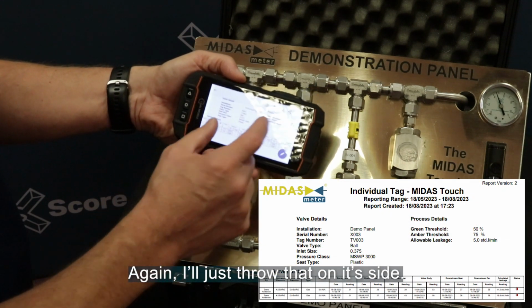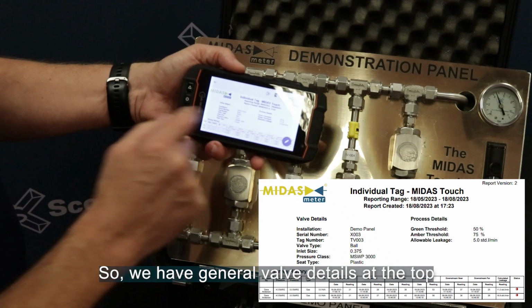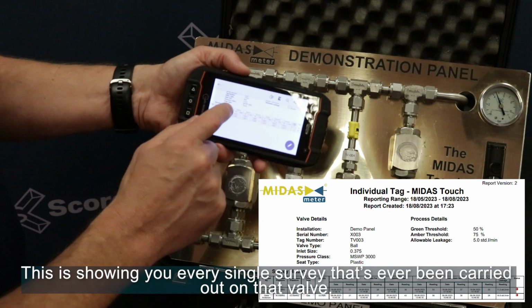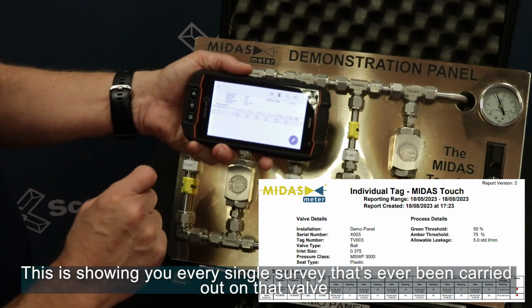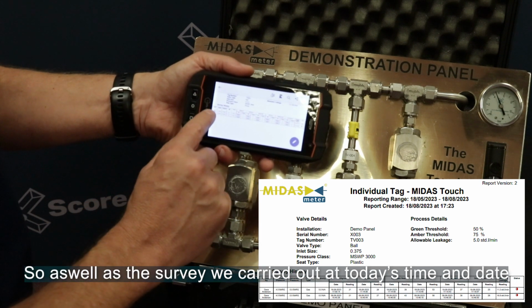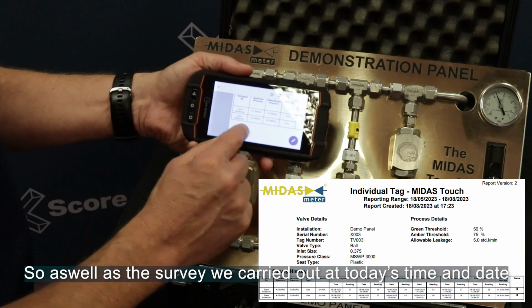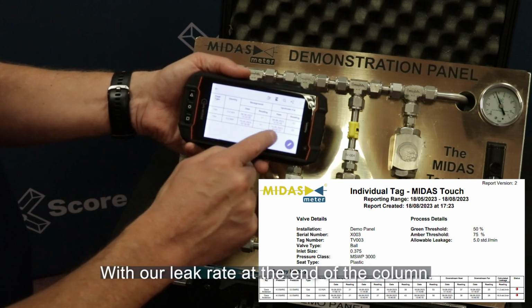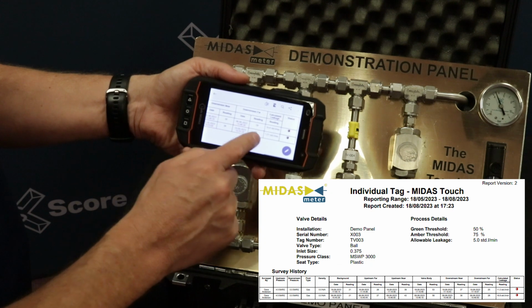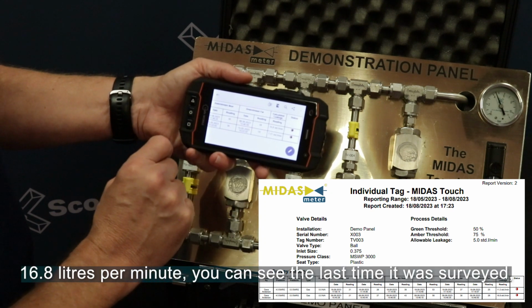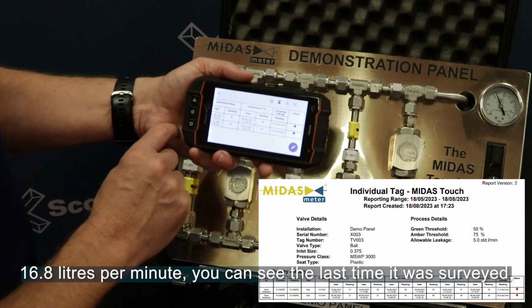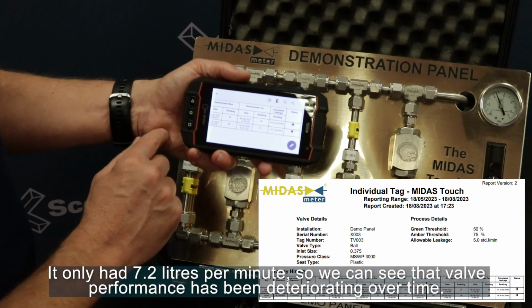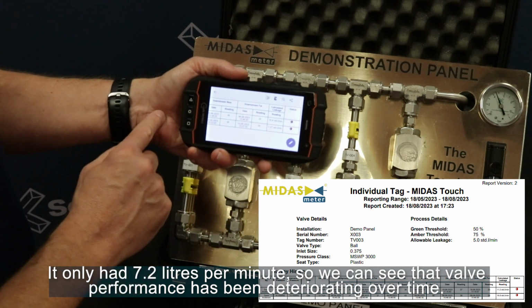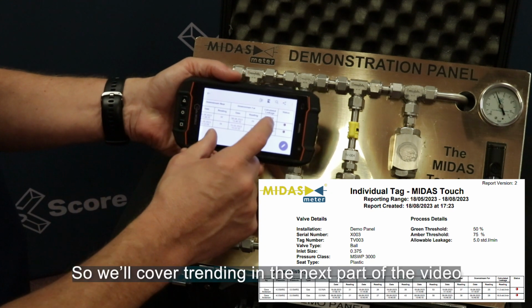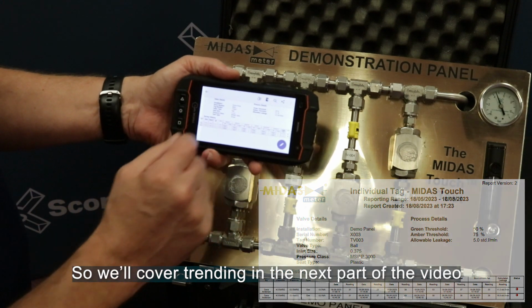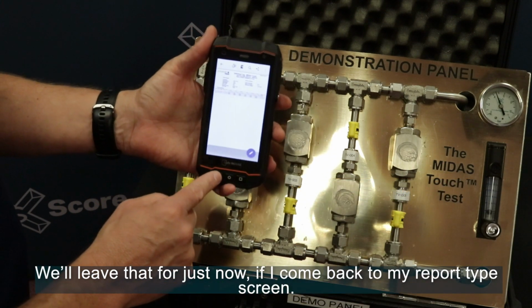Again, I'll just throw that on its side. So we have general valve details at the top. This is showing you every single survey that's ever been carried out on that valve. So as well as the survey we've carried out at today's time and date, with our leak rate at the end of the column, 16.8 litres per minute. You can see the last time it was surveyed, it only had 7.27 litres per minute. So we can see that valve performance is deteriorating over time. So we'll cover trending in the next part of the video. We'll leave that for just now.